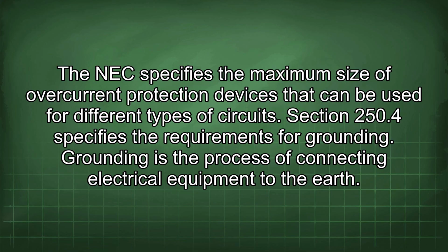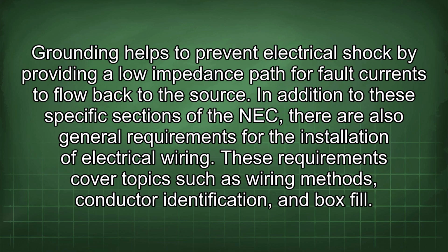Section 250.4 specifies the requirements for grounding. Grounding is the process of connecting electrical equipment to the earth. Grounding helps to prevent electrical shock by providing a low impedance path for fault currents to flow back to the source. In addition to these specific sections of the NEC, there are also general requirements for the installation of electrical wiring. These requirements cover topics such as wiring methods, conductor identification, and box fill.